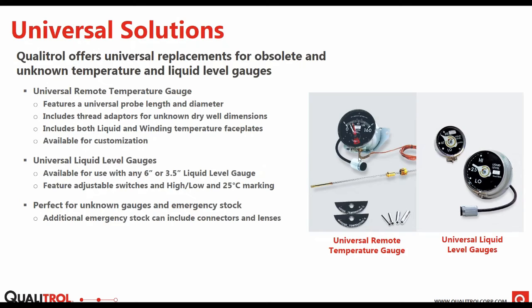So if you wanted to, you could stock some of these for emergency situations, or for really old gauges where you don't know what they were and it's harder to get the specs for an actual replacement, and this will work just fine. This probe will go in. It has sleeve adapters for diameter, and then it's an adjustable length, so it can fit any length well, and then this can be bent down out of the way and installed like a normal probe.